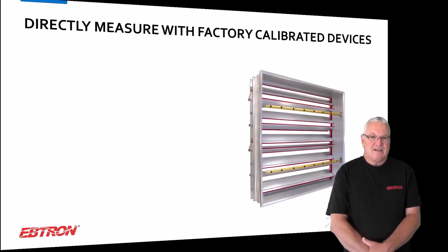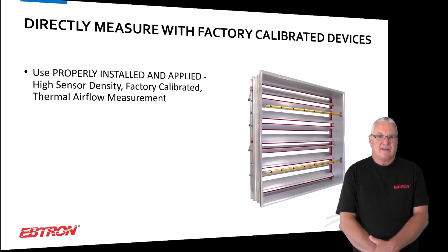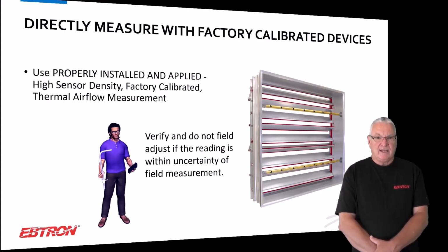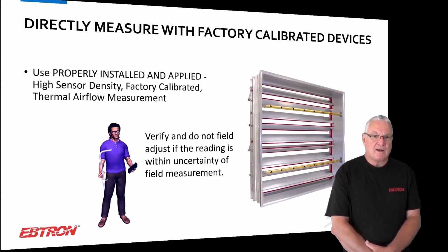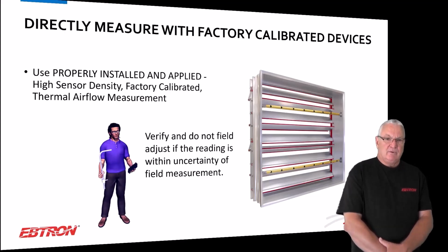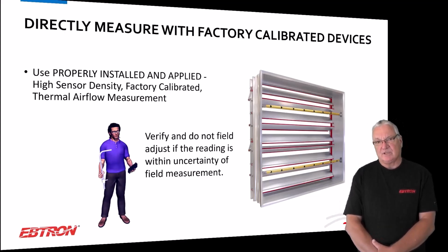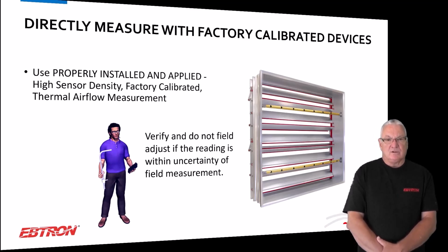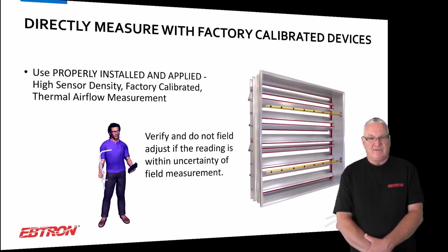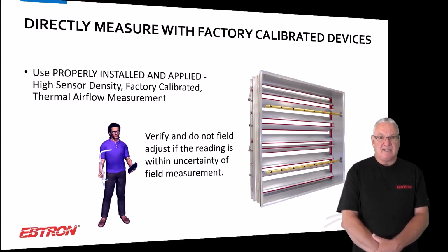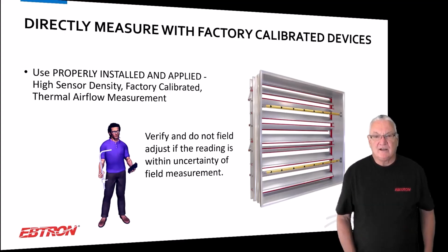And so the right thing to do is directly measure with factory calibrated devices. And that's really where we're at. And we put in the EBTRON, and we verify it. We do want to use test and balance to verify it. We want test and balance to go look at it, take a look at what their uncertainty and measurement is, understand our equipment and say, yes, it's installed properly, and I've done my measurement to the best of my ability, and it's within my tolerance. If my tolerance is 20% on this particular intake, then I verified it, okay?